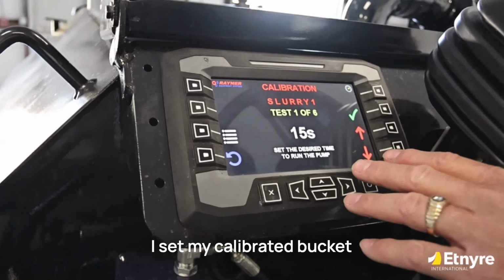I can increase or decrease the amount of time it's going to run. 15 seconds is the default. I can do less, but that's a pretty good average. That's a pretty good number to run with. Don't change it unless you have a specific need for your material, but overall this is pretty good. So I would select this, and then it reminds me, it says using only one new nozzle. I want to make sure we're using a new nozzle. Place the graduated bucket under the single nozzle and press enter to start.